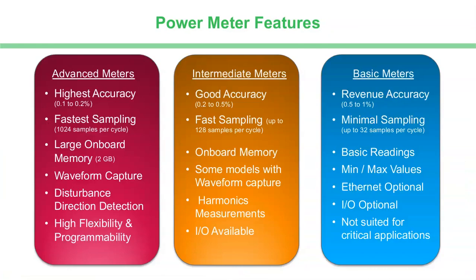So when comparing these different categories of meters, these are the criteria or the ways that I would separate them into these buckets. And the first thing we start with is, what is the accuracy of the meter? So if it's a 0.1 to 0.2% of reading accuracy, that's considered very good, and that would fall into these advanced metering categories. Kind of in the mid-range is this 0.2 to 0.5%. And that's still a very good meter, still provides very accurate readings. If you're simply doing energy submetering, it would then fall into this basic meter bucket. And when you're looking at accuracy for those types of meters, you're always looking for a meter that's better than 1% accurate.